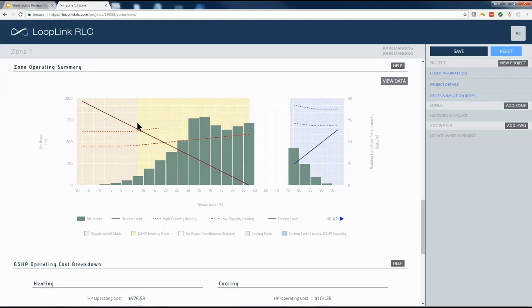So what we mean by balance point temperature, as soon as the outdoor air temperature falls below this point in this tan shaded area, that means the heat pump and the supplemental resistance heat are going to have to run at the same time. But you can see by sliding the balance point temperature all the way back here, we're still not catching a whole lot of bin hours for possible operation in that zone. So even though we're only 80% size relative to the peak heating load, in this last 20% of the load that we tried to pick up with that 5-ton unit, there's not a lot of hours, so we're not really affecting our bottom line in terms of operating costs. So I hope that makes sense.